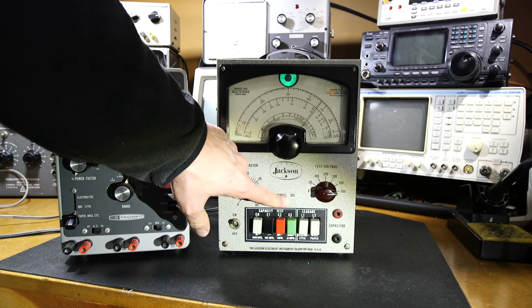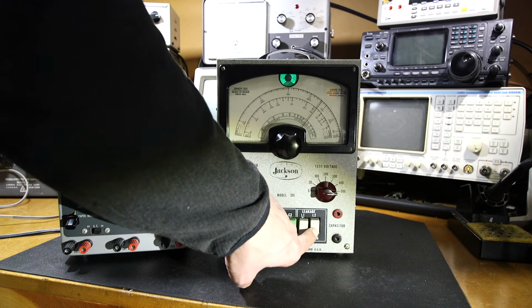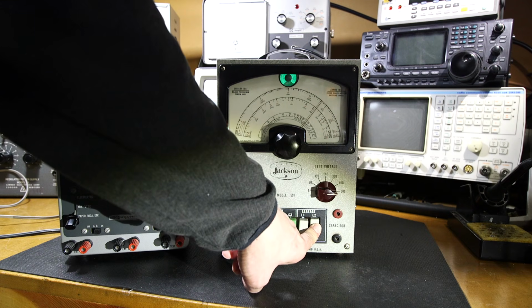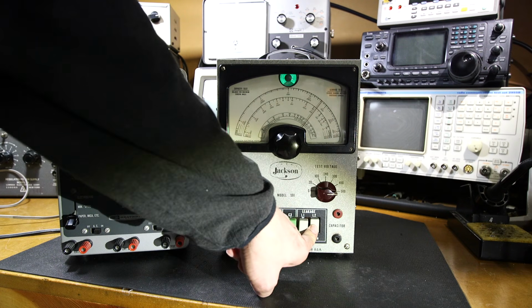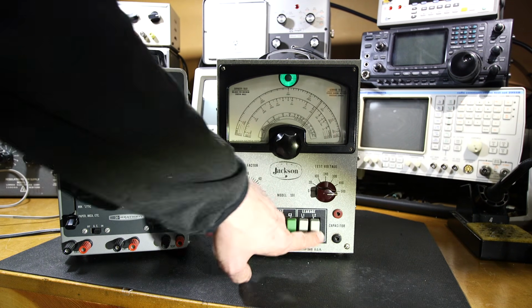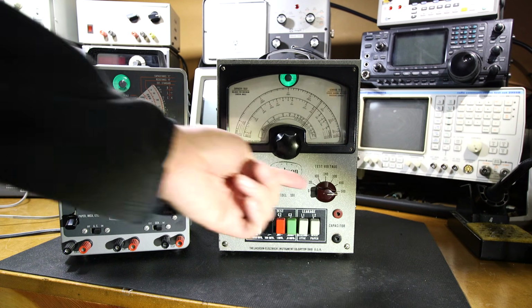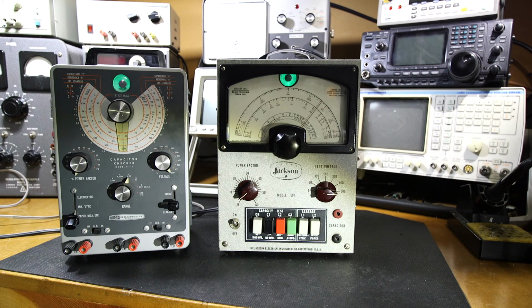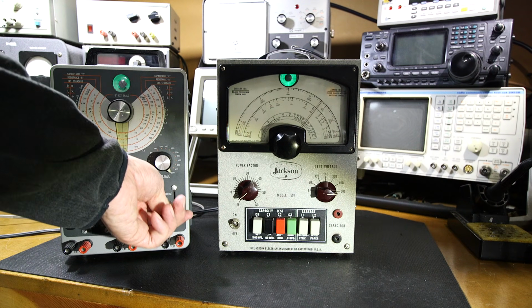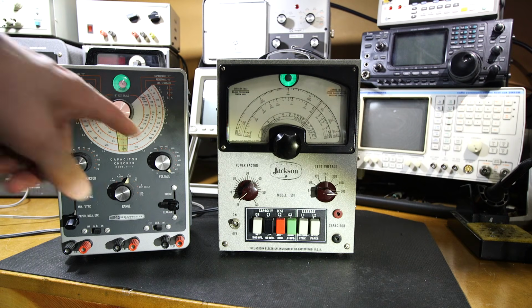The Jackson 591 has a spring-loaded switch. When I push this, it puts voltage on these jacks right now, up to 500 volts. When I let go of the switch, it automatically removes that and discharges the capacitor, much like this, where you have to manually return it to the discharge position.